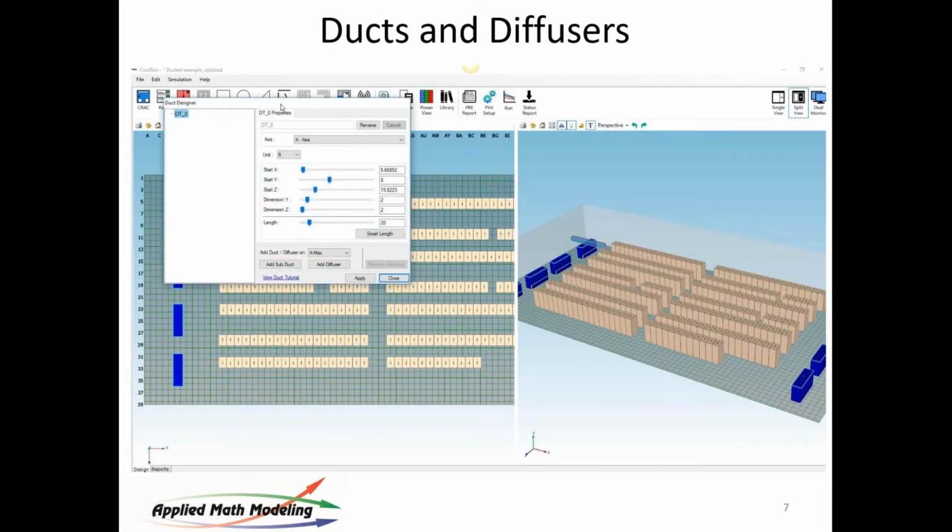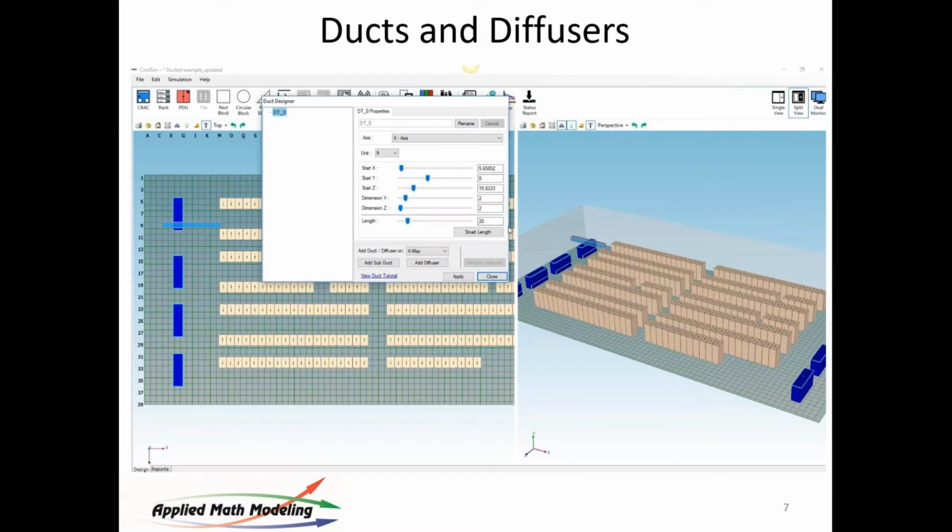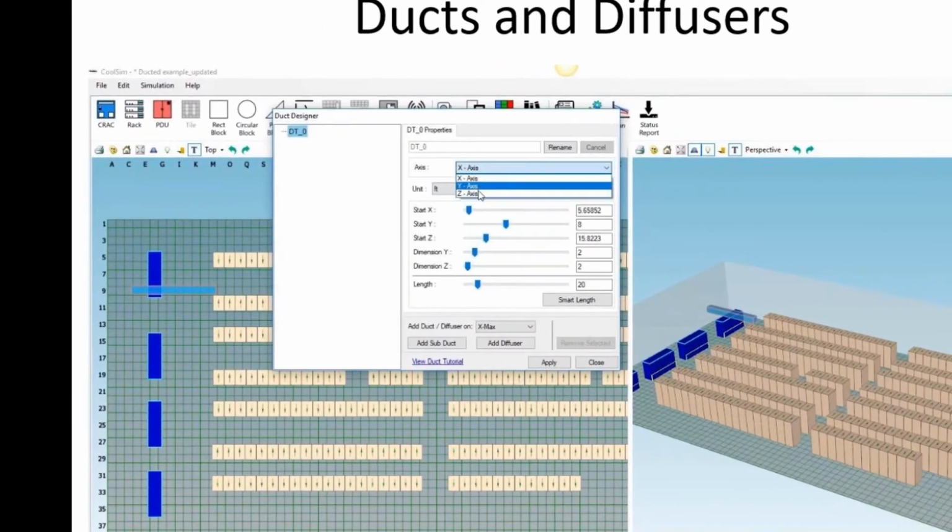And the reason I'm going to put ducts in here is because this model isn't a very good model. This is an upflow, and I've seen these before. This is an upflow design in a classical non-raised data center. And you may say, well, who would ever do that? Well, this is an old site, and yeah, that's how they did it. On a raised floor, they're upflows.